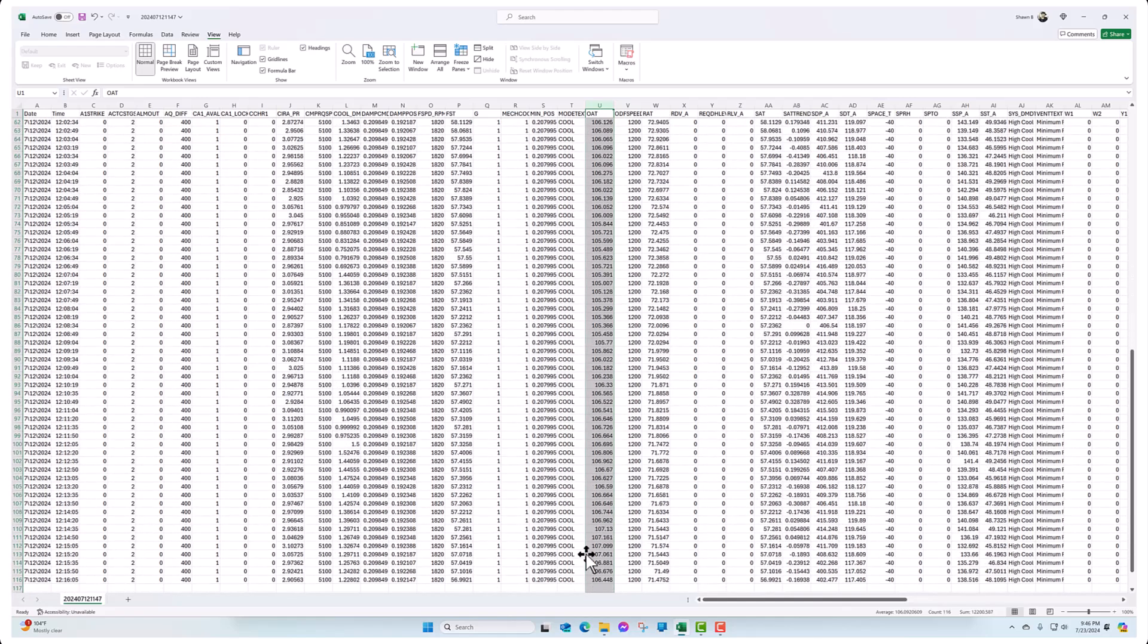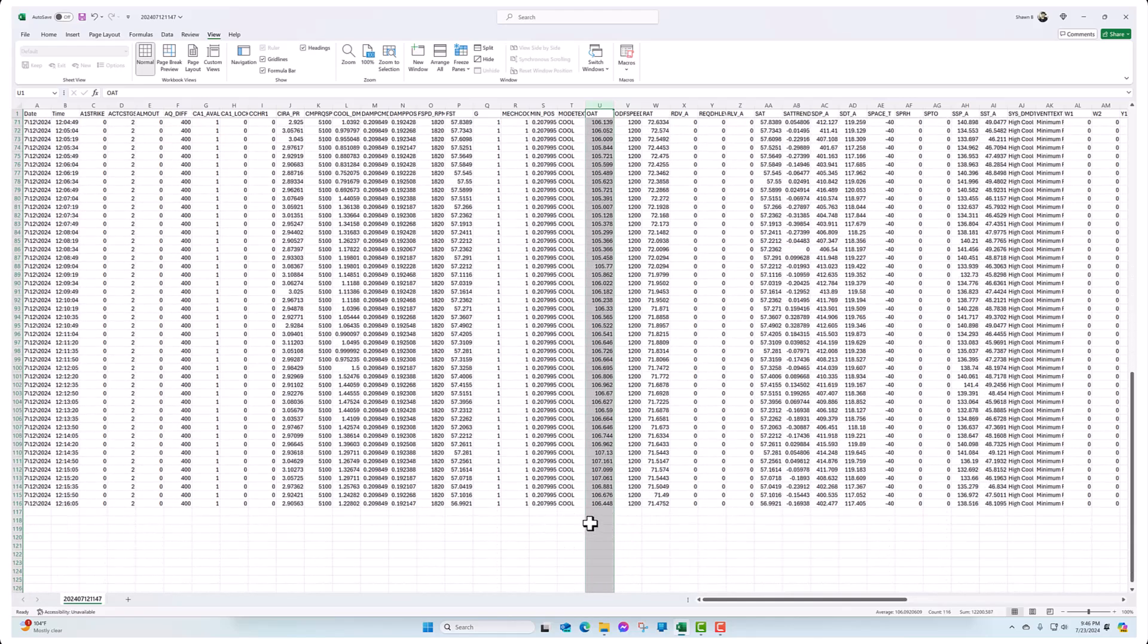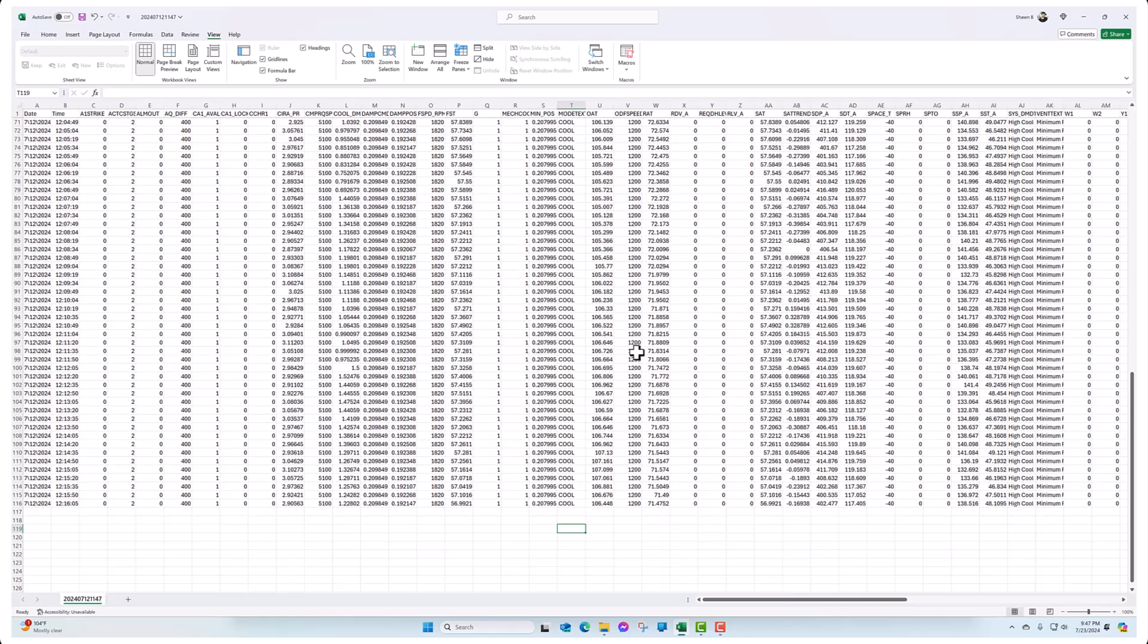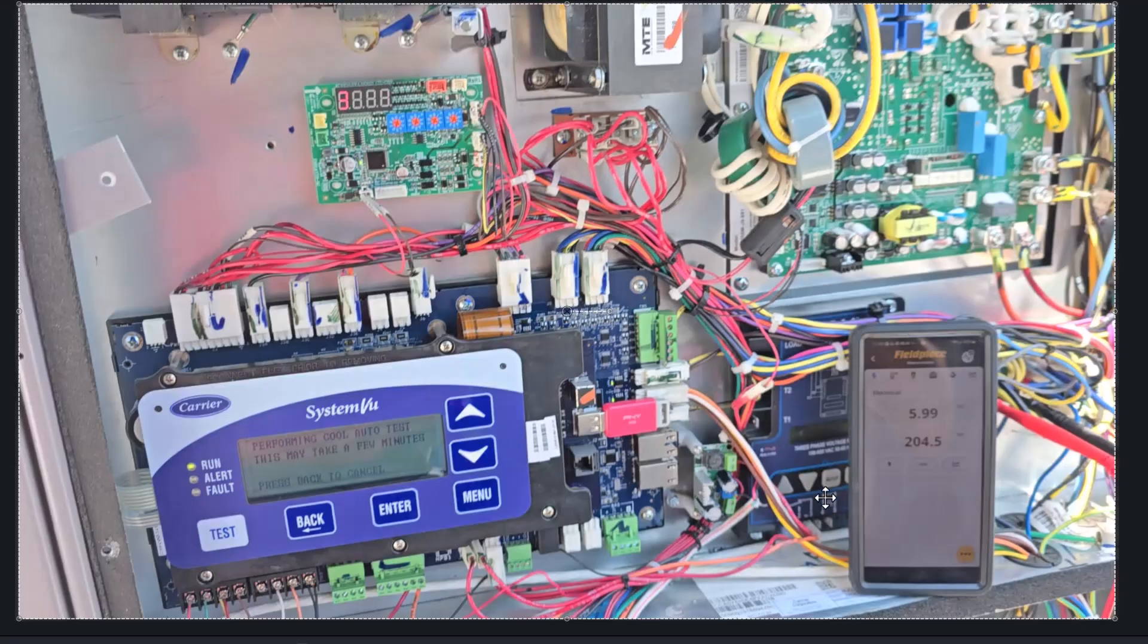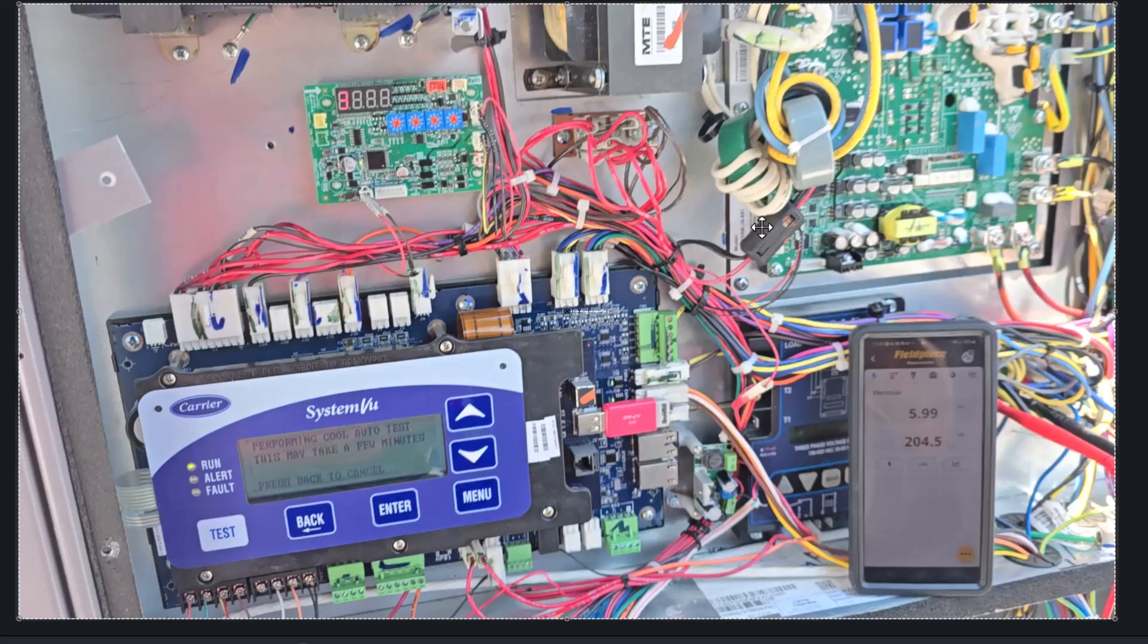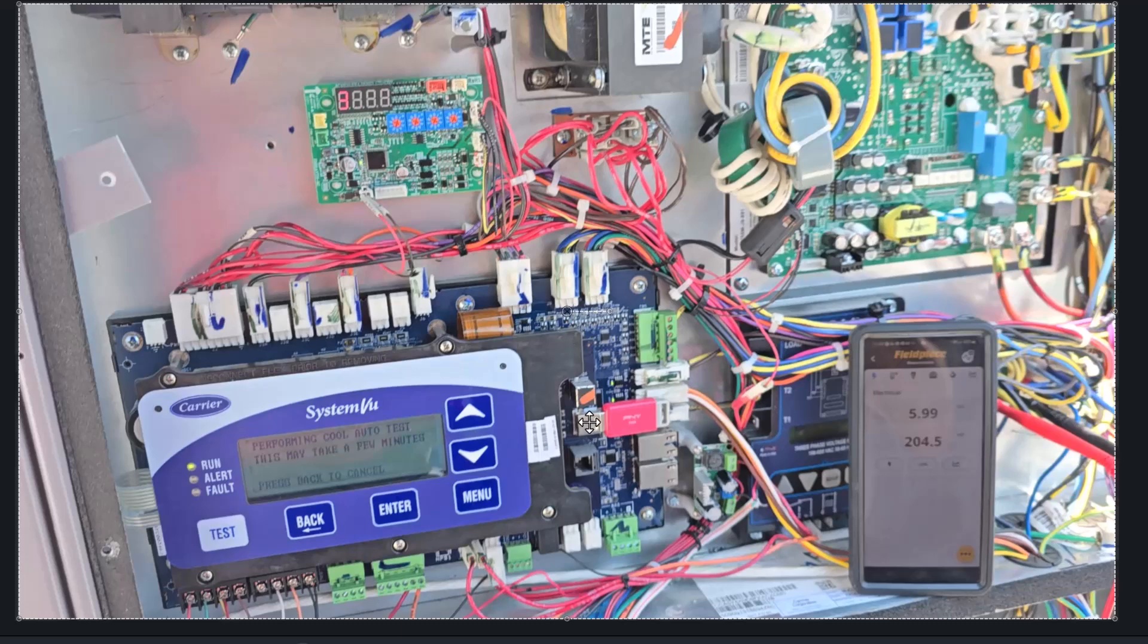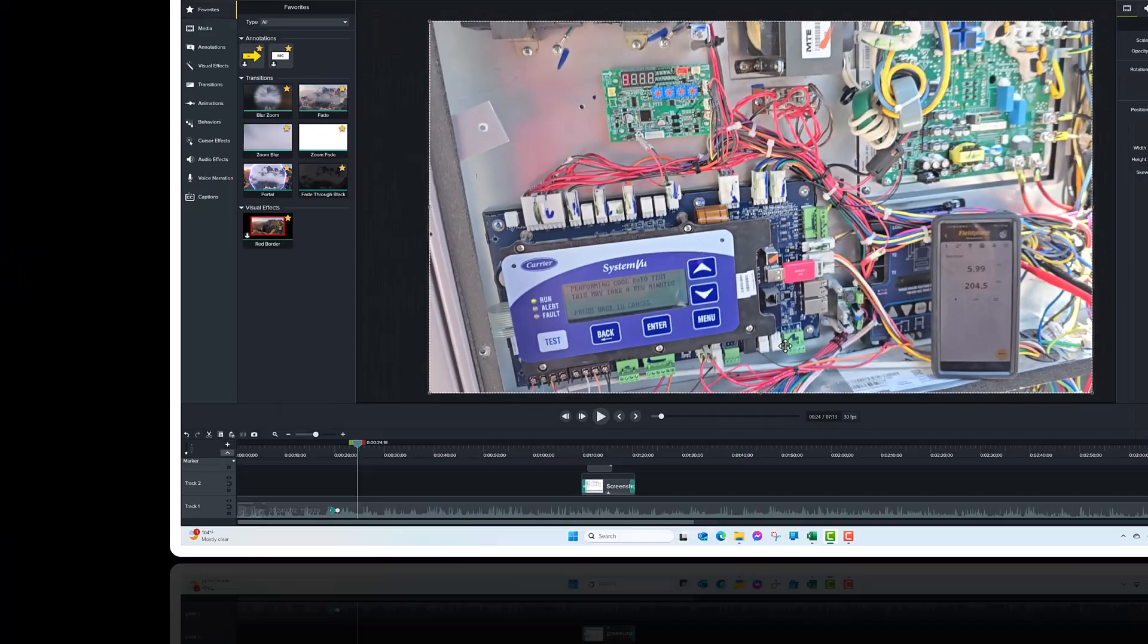So that's kind of what we're looking at there. And then for your alarm or for why the compressor didn't run, you're not going to get that here. You're just going to see when it did and what all the conditions were, the time, the date, what the outdoor temperature was, what the return and supply temperature was. It's still pretty useful information, but again, you're going to have to go to this Emerson board right here, which is got two-way communication RS-485. If this faults out, the inverter board that's driving the compressor, it's going to display error code. It's going to be like E-19 for like compressor current foldback. It's like it's trying to slow down and keep itself from tripping, but it couldn't. So you get that fault, which seems to be a pretty popular one in the desert in the heat.